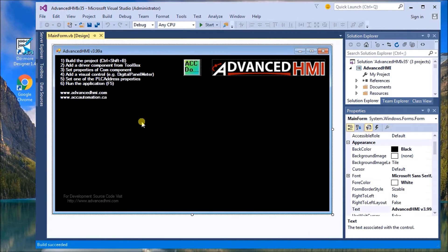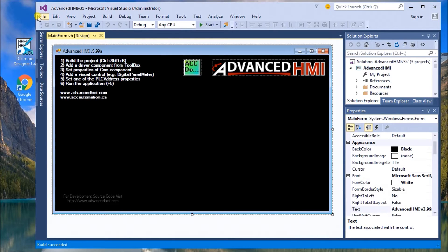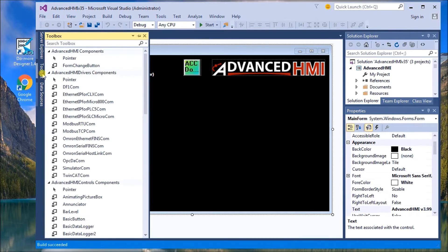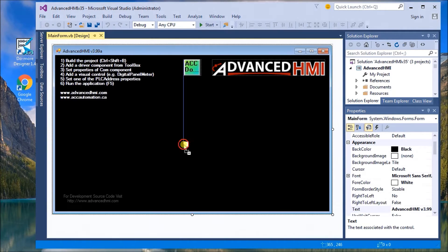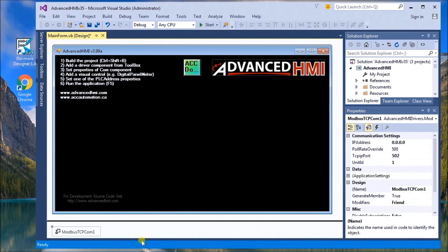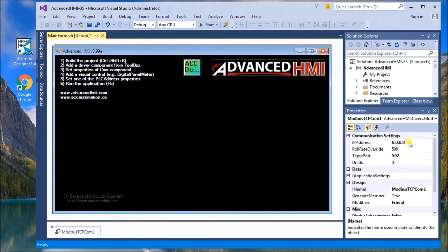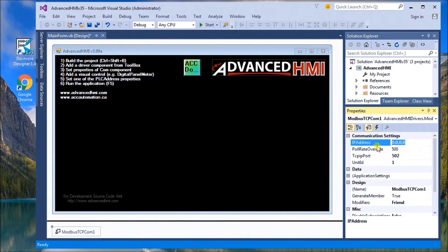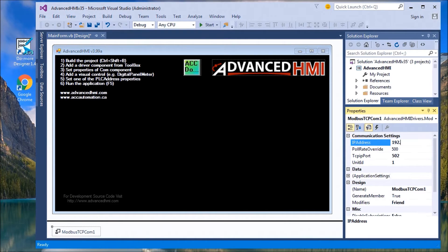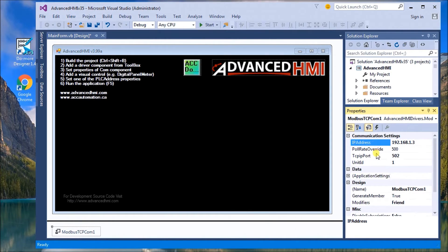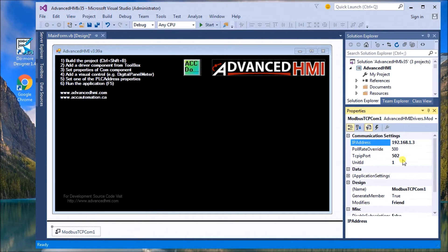And so it's all built. Then what we'll do is we're going to add our driver to it. Under the left-hand side here, we'll hit toolbox. We'll go to Modbus TCP and we'll drag this onto the form. You'll notice it comes down here and now we can assign the IP address. Now I know our address for the PLC is 192.168.1.3 and the default port is 502.